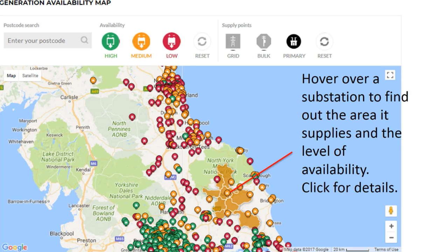So do make sure you find a substation locally and hover over it to find out how constrained it is. If you then click on the substation, this window pops up, the one that I've highlighted in red. It has a number of features, characteristics of that substation, and there's a big bar there in black that says downstream. If you were to click on the upstream bar, that view would change to the extra one on the right-hand side that I'll talk about in a minute. I've just popped them both on the screen here so you could appreciate that there are two different views, and it's important that you look at both.